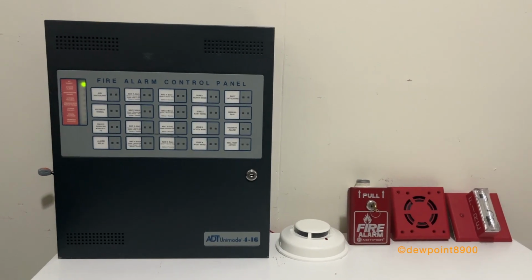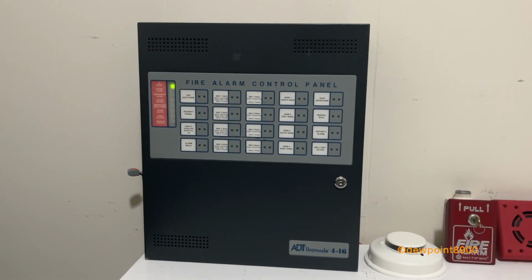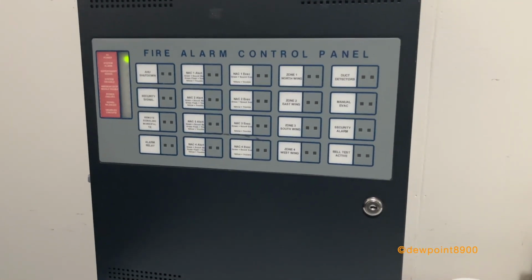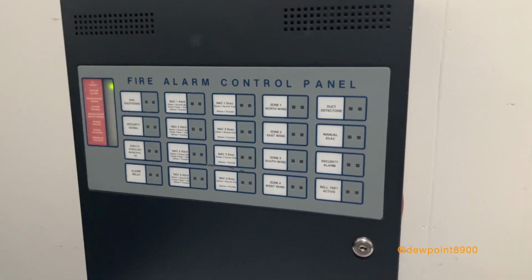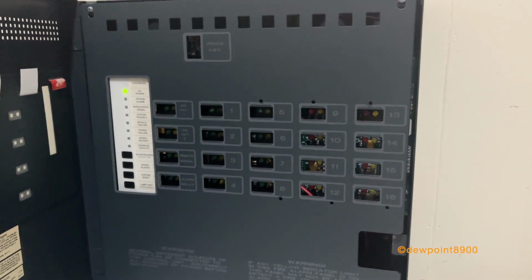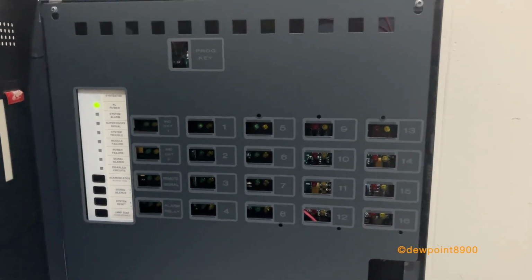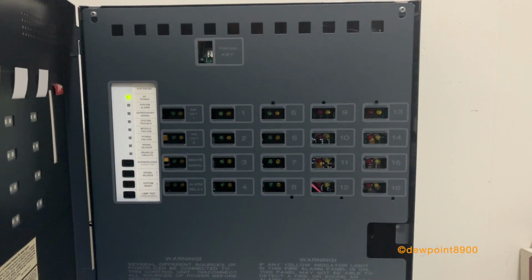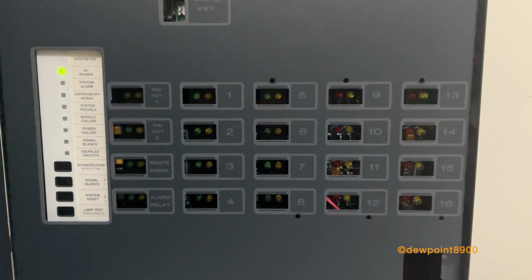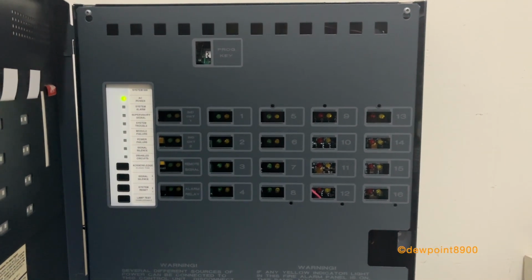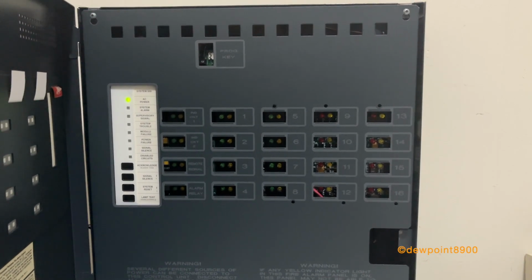For the next demonstration, we have the ADT Unimode 416, and it's configured for 2-stage signaling. So this one uses the same old-style cabinet, although this particular panel is a little bit newer. I think this one was made in 1996 or so. And it came with this dress panel, which is pretty neat. So the layout is nearly identical to that System 500, but instead of having an IC4 signal card, there's a TC4 timer card back there. And that card can be used for either 4 releasing circuits or 4 signal circuits for 2-stage signaling. In this case, the latter.